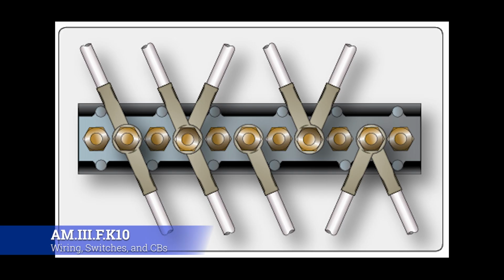Terminal blocks are a place where it's very easy to induce electrical faults and start fires, because especially on your higher amperage terminal blocks, you have these connectors that by nature are going to be exposed, and it's very easy for something to get on them and cause a short, or for them to touch each other. I've seen more than one fire start because of a high amperage terminal block where something was either dropped on it, leaked on it, or somebody installed something incorrectly.